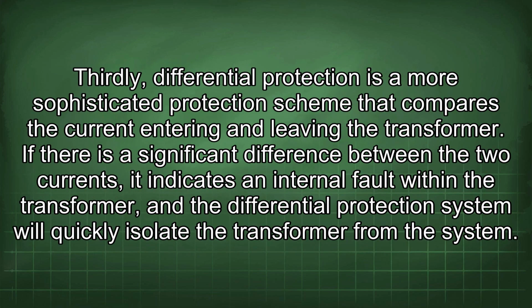Thirdly, differential protection is a more sophisticated protection scheme that compares the current entering and leaving the transformer. If there is a significant difference between the two currents, it indicates an internal fault within the transformer, and the differential protection system will quickly isolate the transformer from the system.